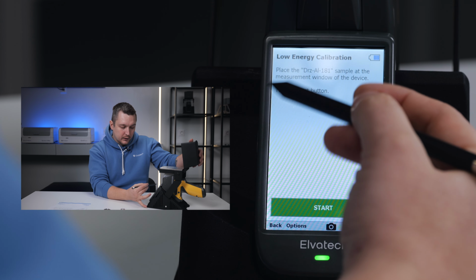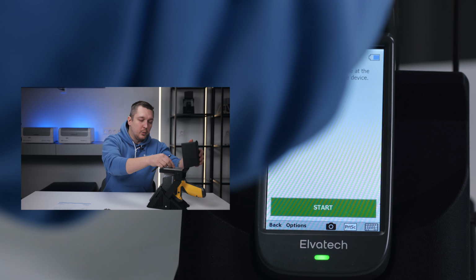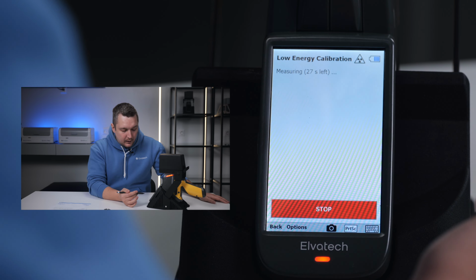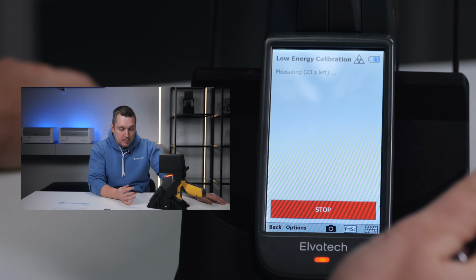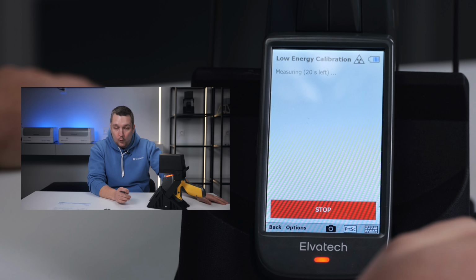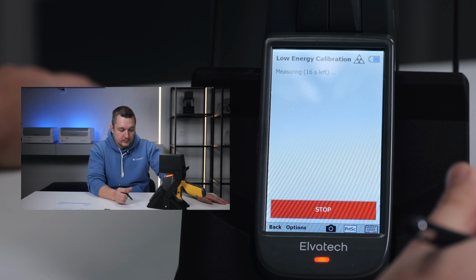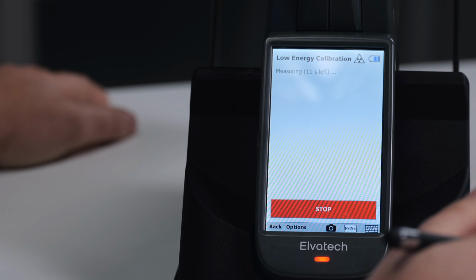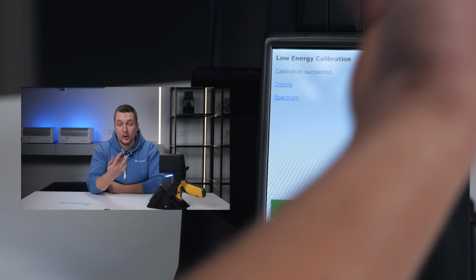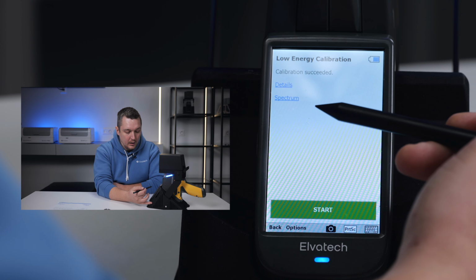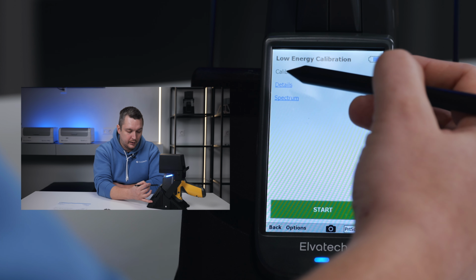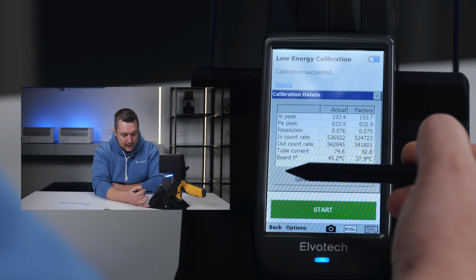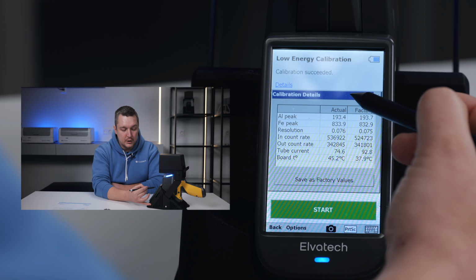And we just click on the low energy calibration, and here we need to place the 2024 aluminum alloy. And the procedure is the same. We just click the start button. And this procedure takes about 30 seconds for the light elements energy calibration. And we just wait. And we are done. So the calibration succeeded, and we have the same info on the screen. So we click also on the details. And here we see the same table, but with different information. Here we have the aluminum peak, ferrum peak, resolution, and so on. And also we have actual values and factory values.